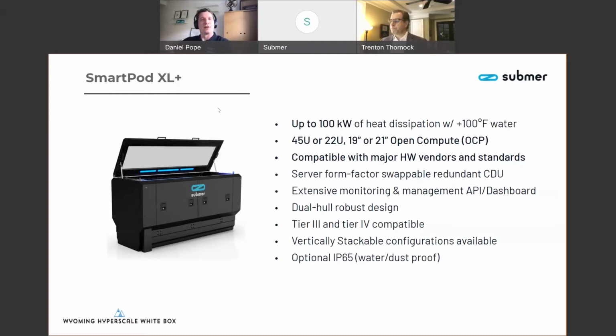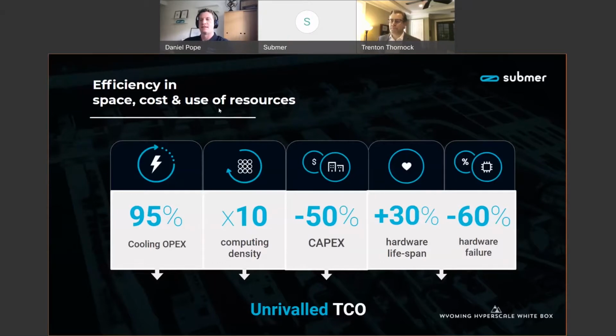Awesome. So on the next slide, what we have are the typical benefits we see in immersion. There's the huge reduction in cooling OpEx, which comes primarily from the simplicity of the end-to-end installation on the cooling loop. Fewer components, and those components leverage dry cooling infrastructure for the secondary cooling loops. The efficiency of transmitting heat from liquid to liquid, with no air involved, drops the cooling cost substantially.